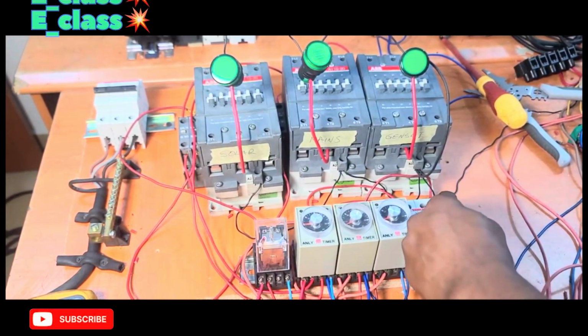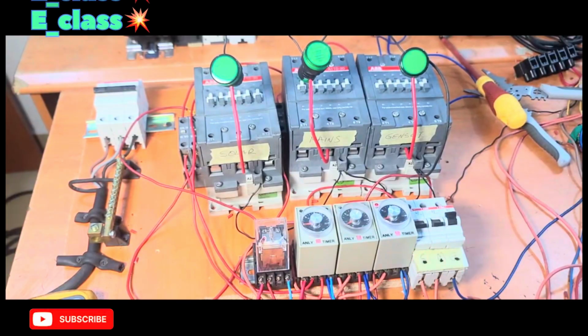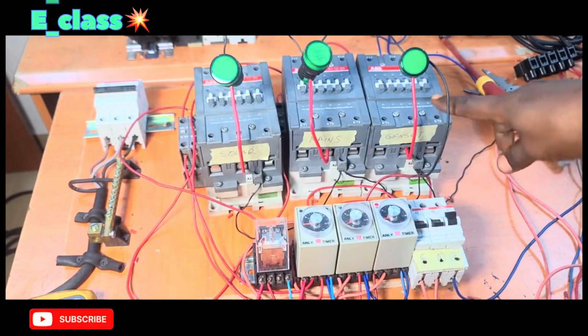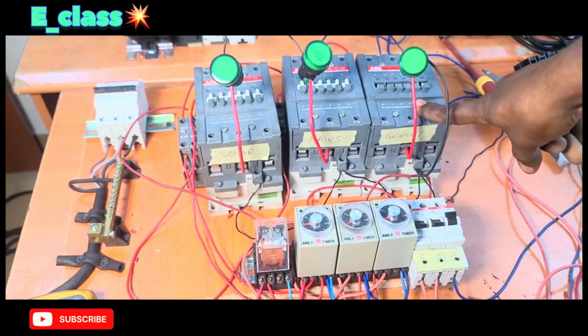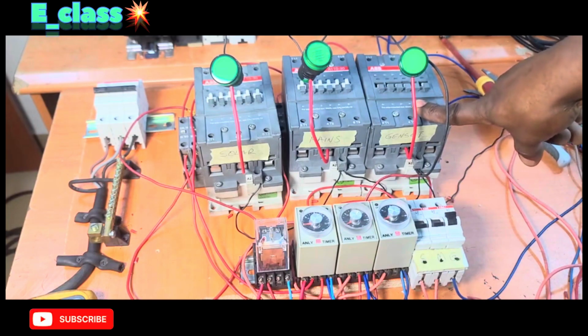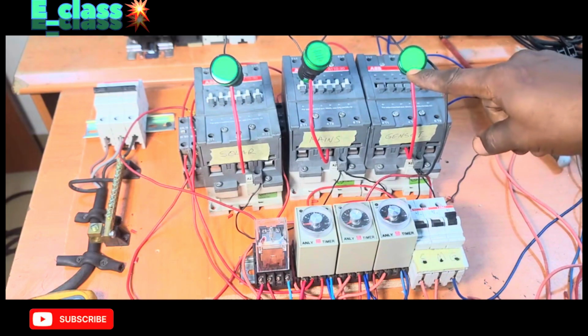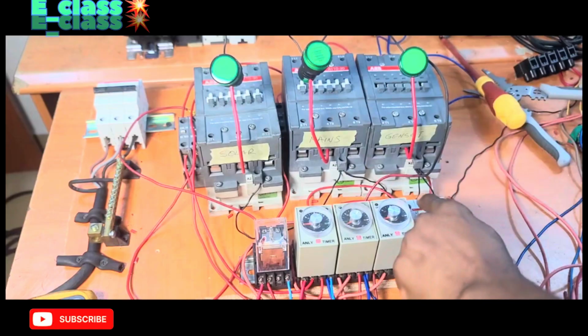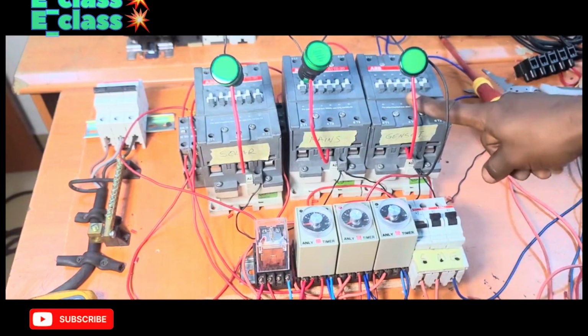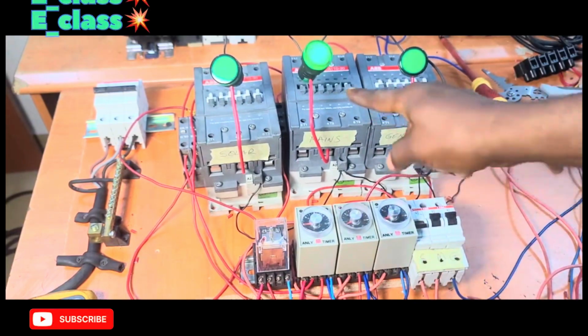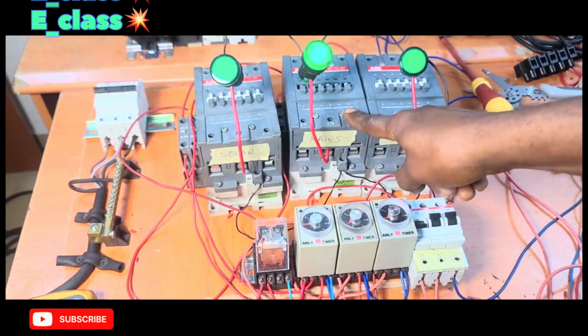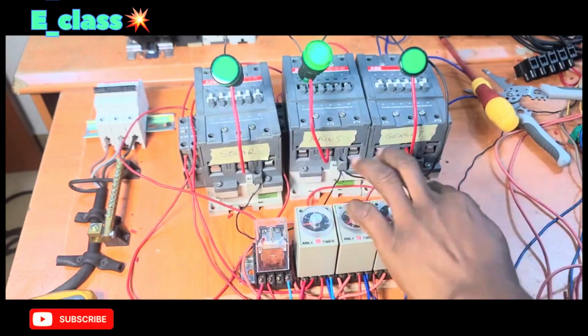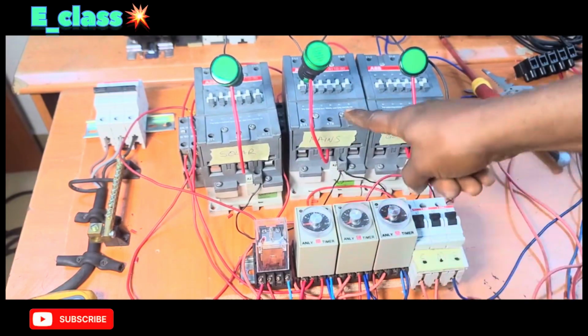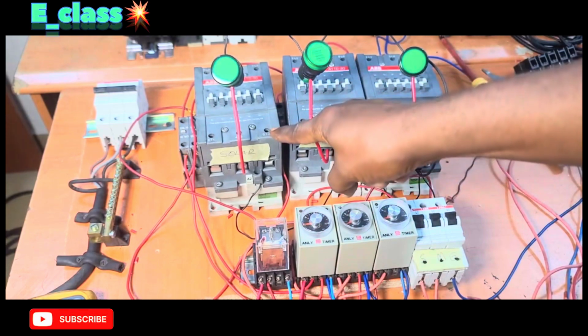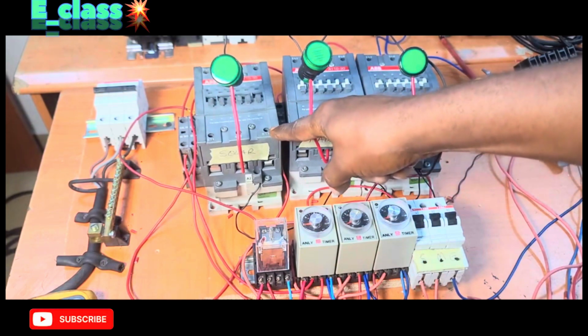We energize and we wait for the delay time, and this one is activated, so we have power. Let us energize this one. This one has disconnected instantly, and this one has made after the delay. Let us activate this one. This one has disconnected, and this one will connect after the delay.